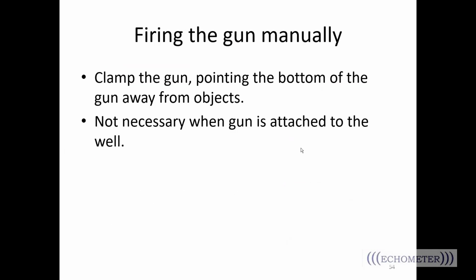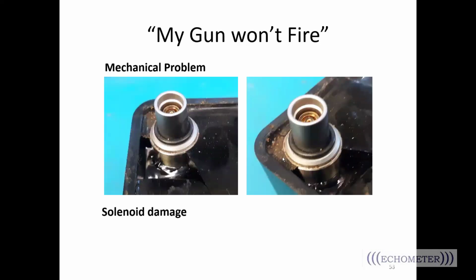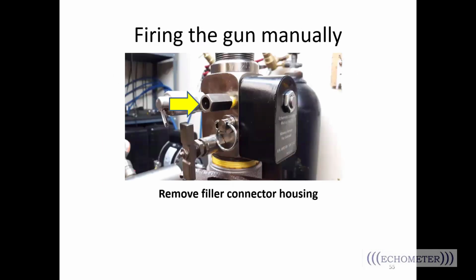When there's a failure on the gun, we've just had so many times that operators have called in and said, my gun won't fire. There's something wrong with the gun. Something is preventing the gun from operating properly. And so now they have a gun with six or seven, however many hundreds of pounds of pressure, that is loaded and will not fire. Under these circumstances, yes, we would absolutely prefer that you not fire the gun manually. The remote fire gun was not meant to be that way. But in the event that you have a gun with pressure on it that won't fire, this is a way for you to make the gun safe, if you need to send it in to us for repair.